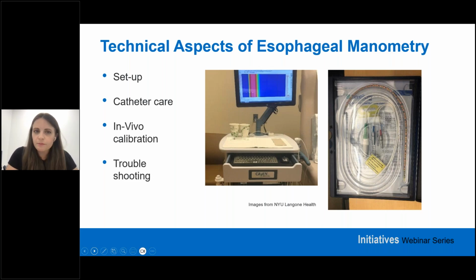Also, another reason people receive errors for calibration is they chose an incorrect catheter to match up with the software. If you have multiple catheters in your clinic, and you choose a catheter on the system that does not match the actual catheter that's plugged into the program, it's going to malfunction. So it's important to double check that as well.